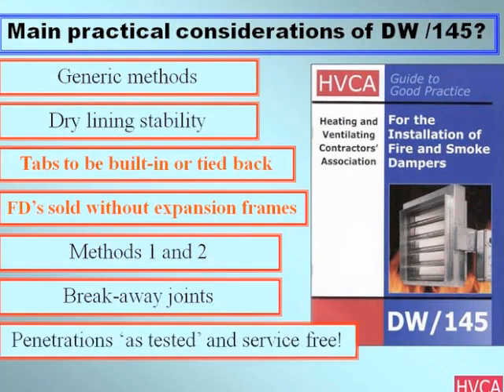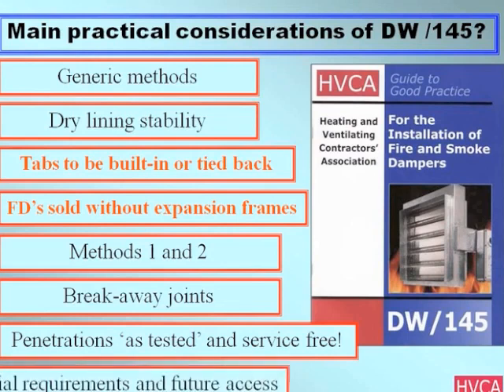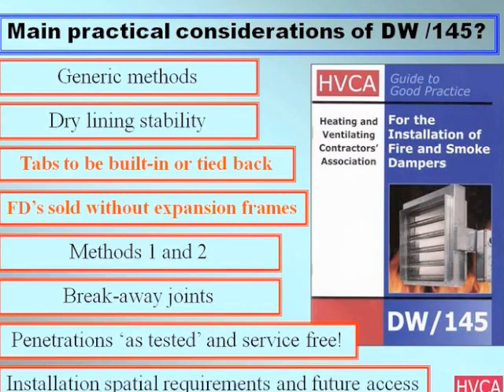The penetrations must be as tested, and they must be service free. Every fire damper manufacturer tests their product with a specific penetration seal, and there mustn't be any other services passing through that aperture. If you come to fit a fire damper and find the electrical or pipework contractors have run services through that aperture, that needs to go back to the CDM coordinator to establish what must be done—more often than not, removing those services and running them through a different route. It's easy for some contractors to pick the closest available hole, but for fire protection it's important these issues are recognised.